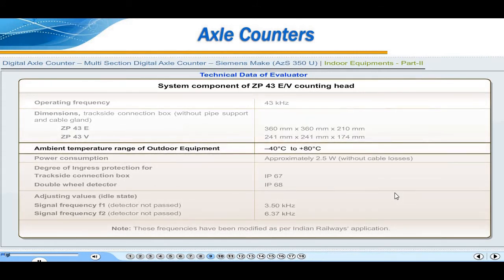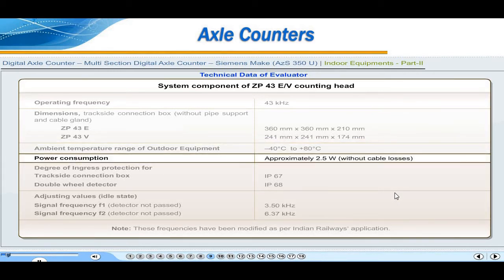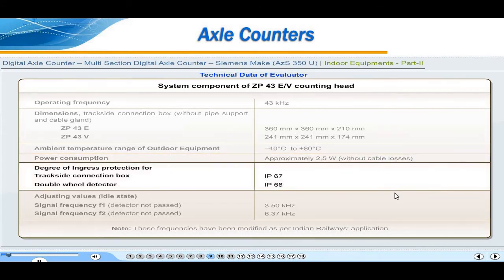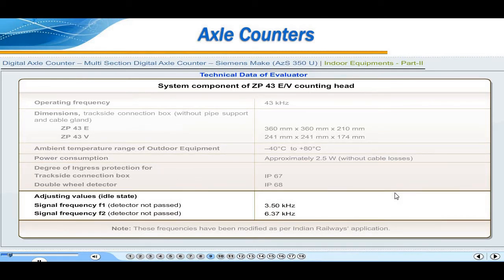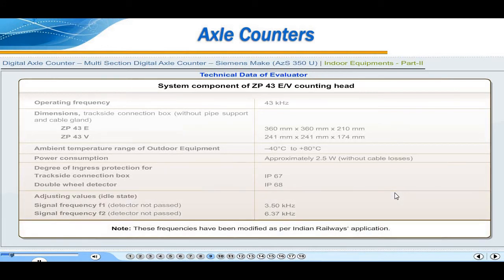Ambient temperature range of outdoor equipment is minus 40 degrees Celsius to plus 80 degrees Celsius. Power consumption is approximately 2.5 watts, that is without cable losses. Degree of ingress protection for trackside connection box is IP67. For double wheel detector, it is IP68. Adjusting values in idle state. For signal frequency F1, when detector not passed, it is 3.5 kHz. For signal frequency F2, when detector not passed, it is 6.37 kHz. These frequencies have been modified as per Indian Railways application.